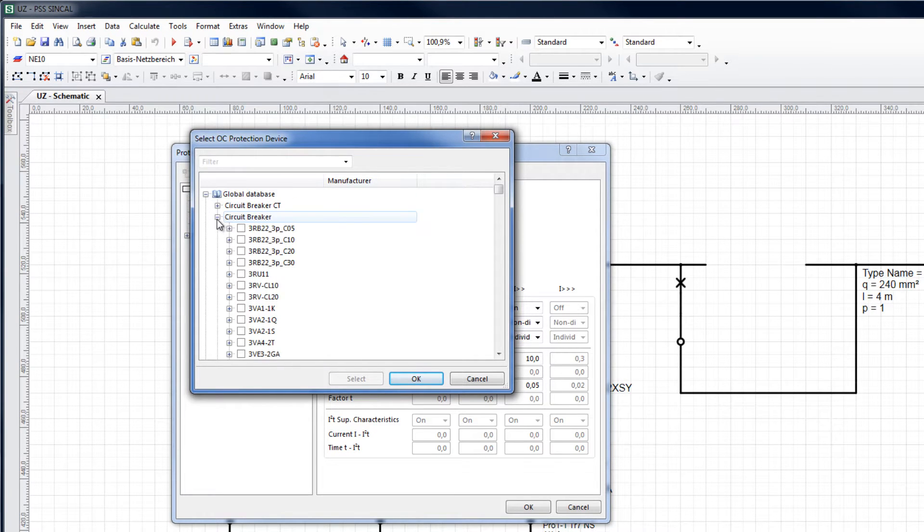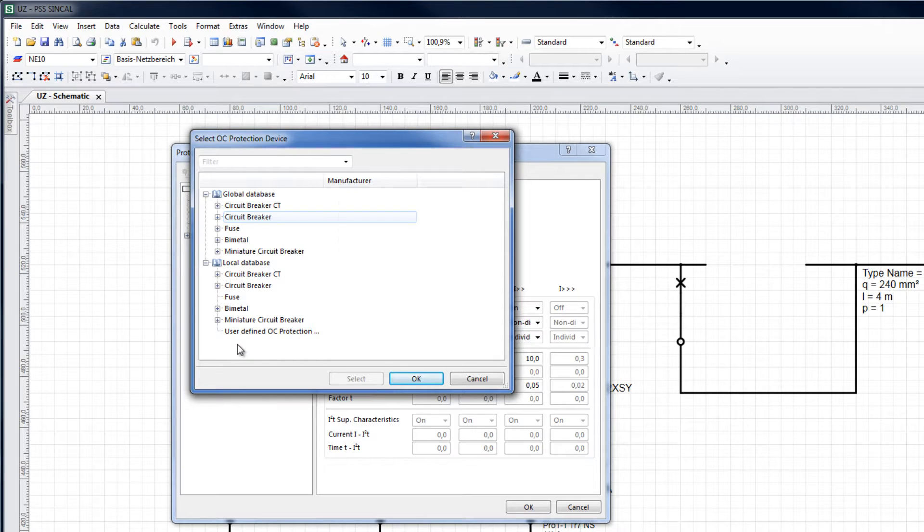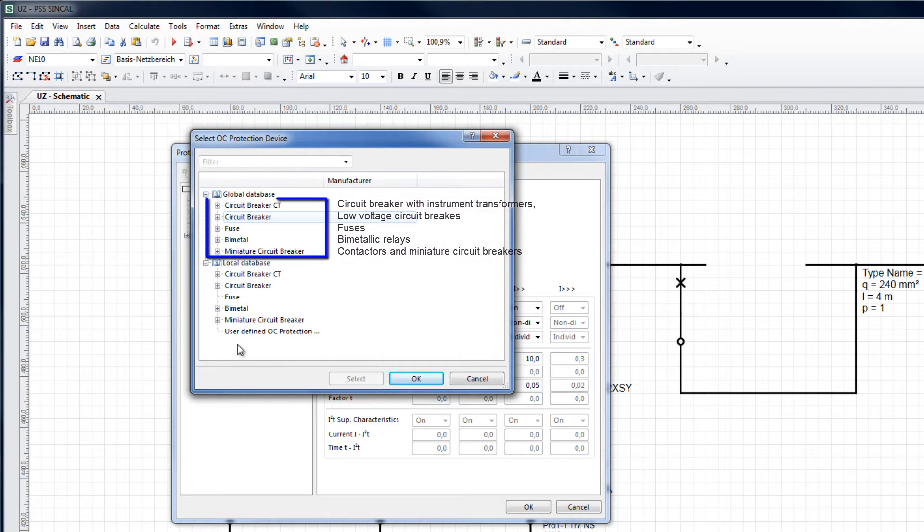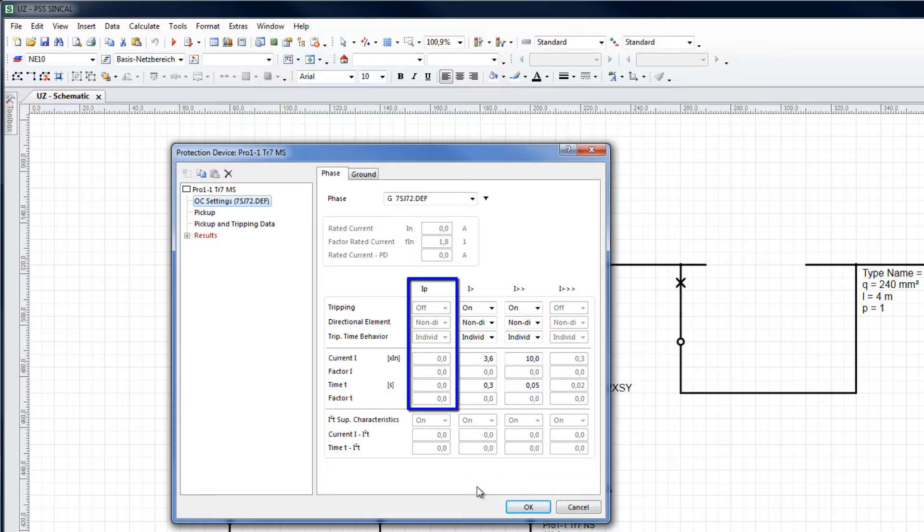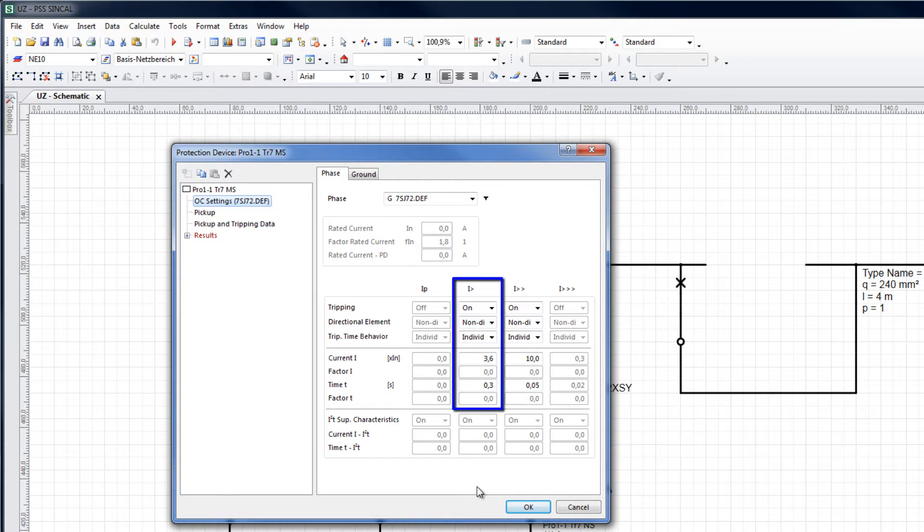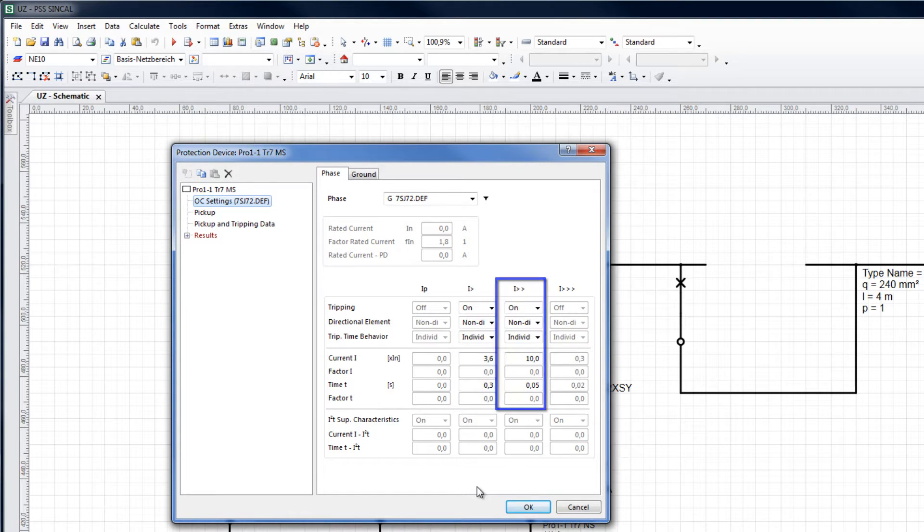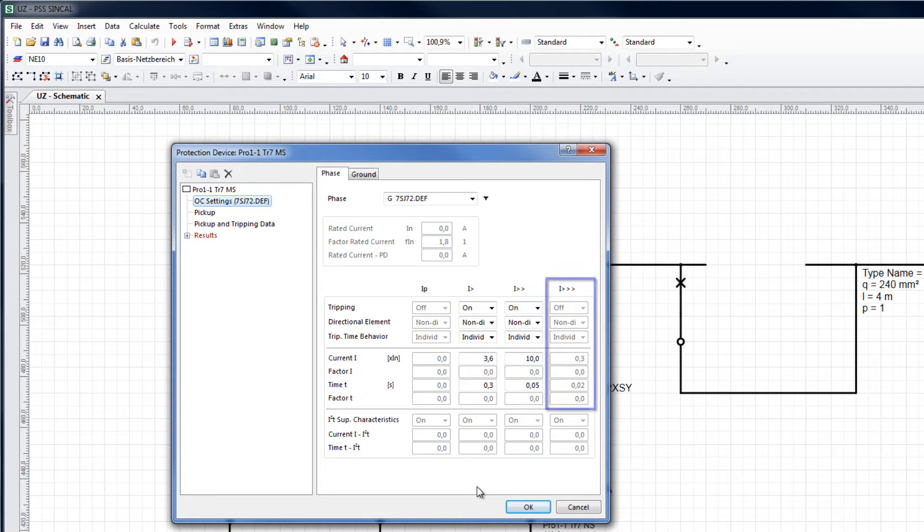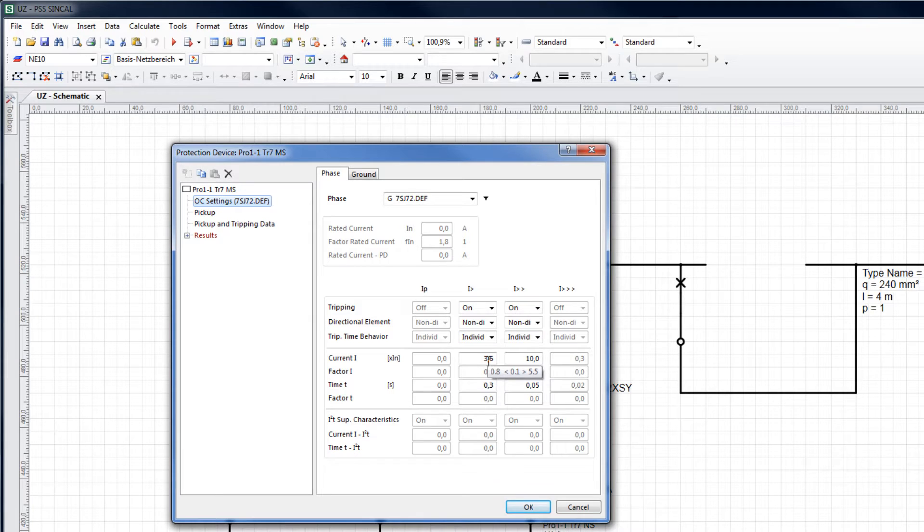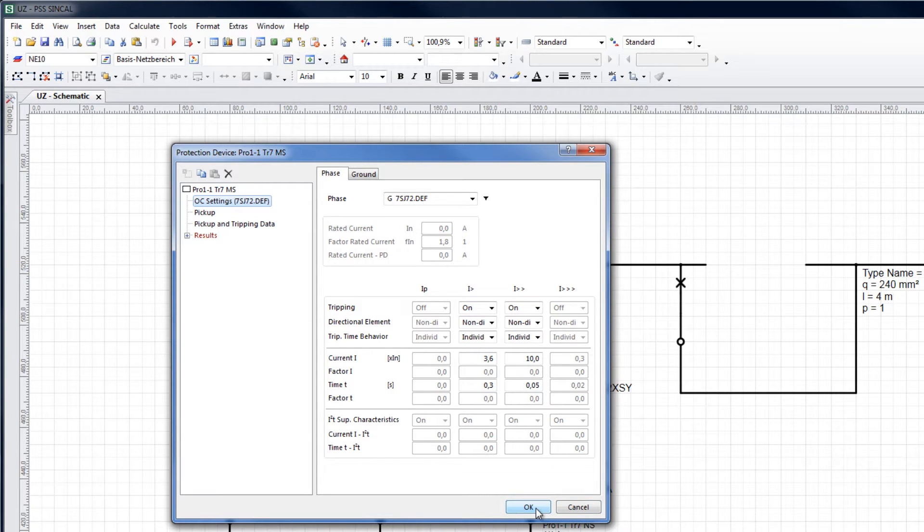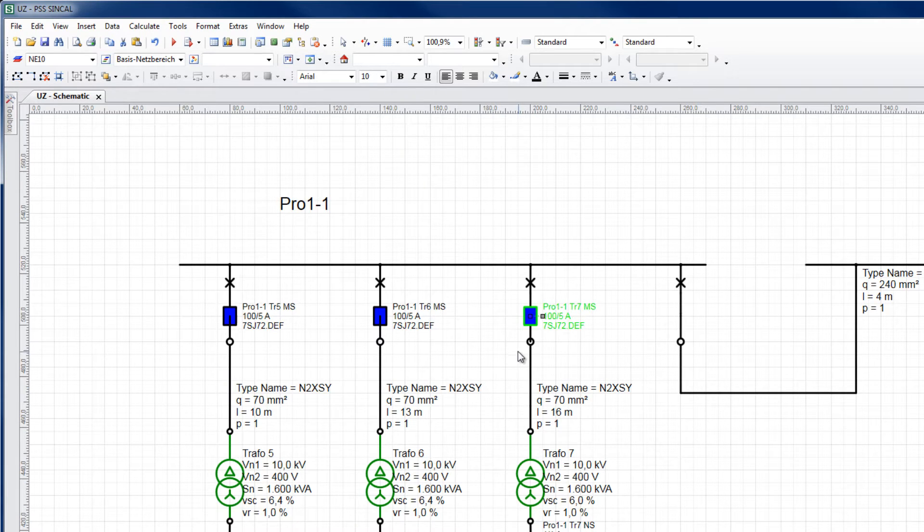Various types of devices are available in the database. Once selected, the types of tripping supported by the device, for example, characteristic curve, first instantaneous, second instantaneous, third instantaneous, as well as the valid setting ranges are automatically loaded, and those types not supported are greyed out. Float the mouse over the settings field to display the range of possible settings that the physical device supports. SINCAL will check and only allow setting ranges within the supported range.